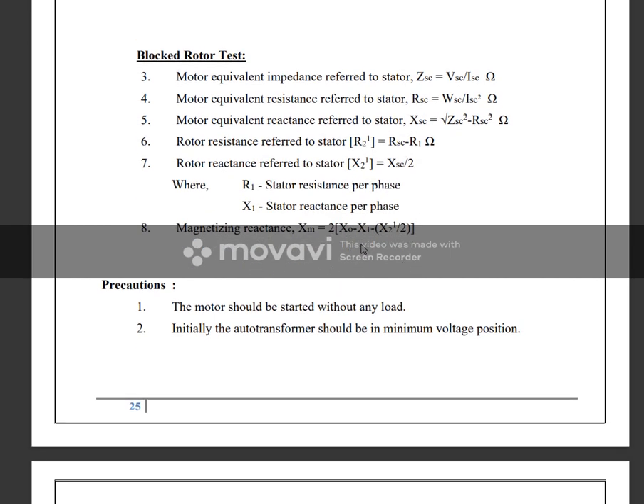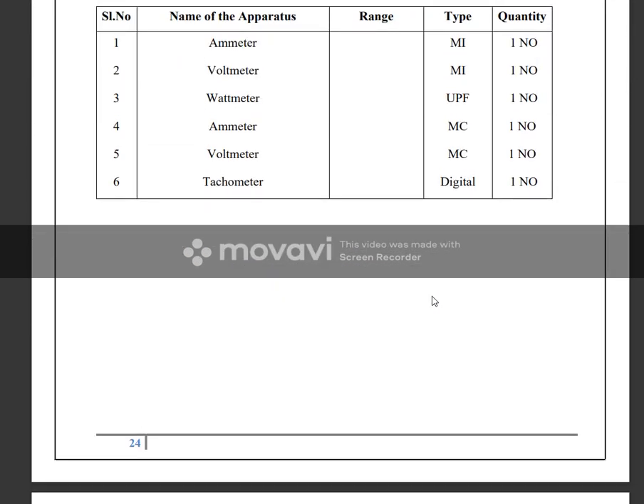From the locked rotor test, we find the equivalent resistance referred to the stator. Rotor resistance referred to stator equals RSC minus R1, where R1 is the stator resistance per phase. Also X1 is the stator reactance per phase, X2 dash equals Xsc by 2. We know that slip S equals (ns minus n) by ns, so you can calculate accordingly.